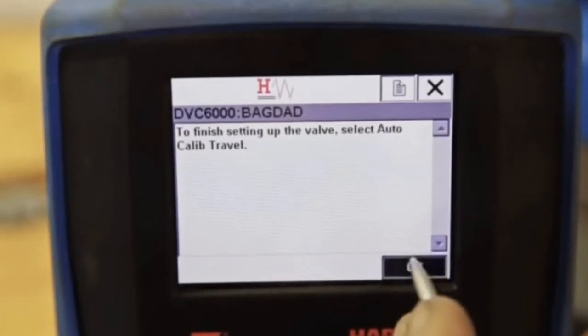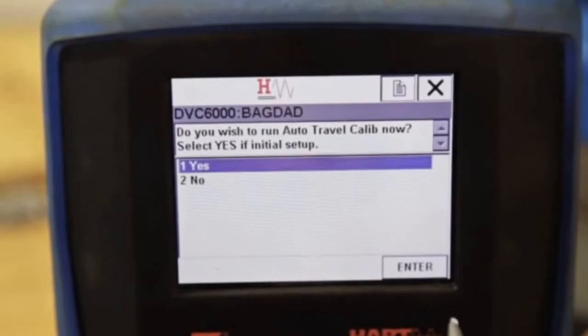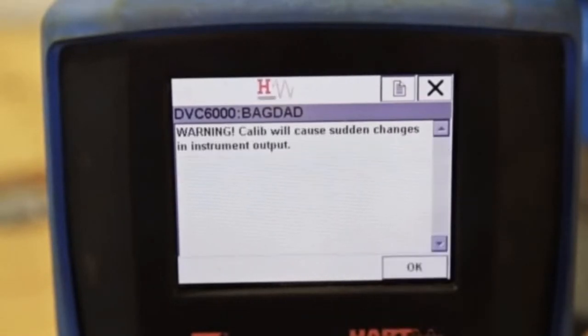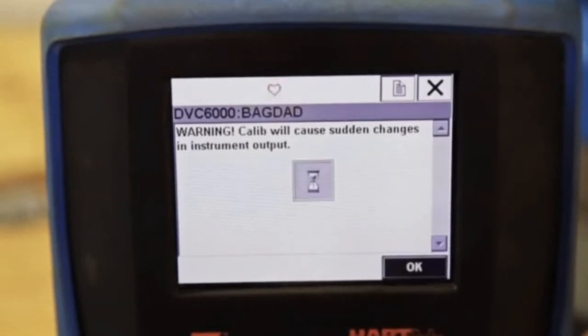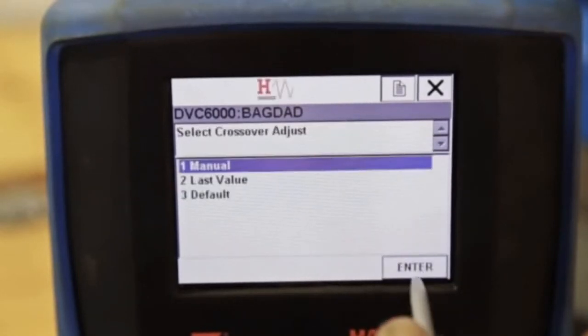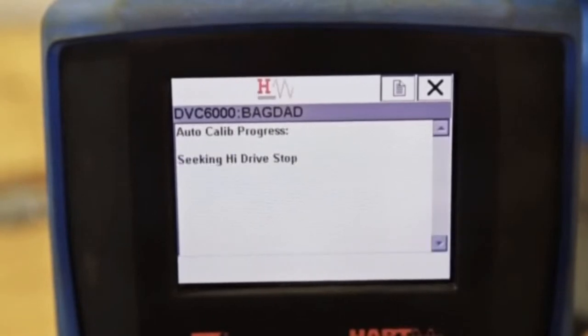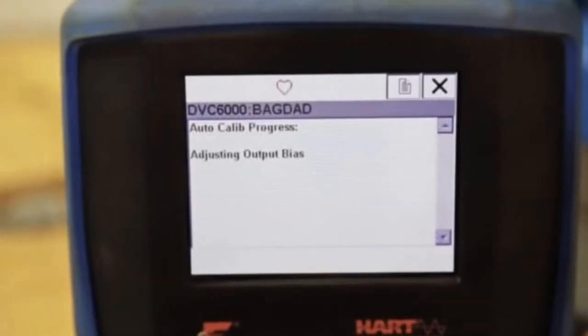And once more. Select Yes to run the auto calibration. A warning screen will appear. Calibration will cause sudden changes in instrument output. Select Manual for crossover adjustment. The valve will move to seek the high and low drive stops and adjust the output bias.